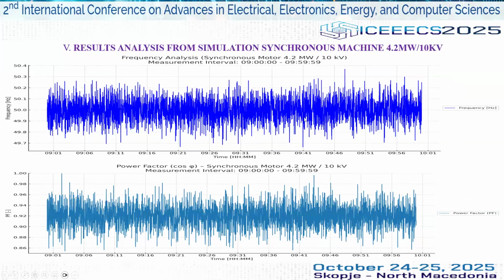The next picture illustrates the frequency analysis. The value remains very close to the nominal level of 50 Hz. The last picture presents the power factor. The power factor value remains high for most of the interval, indicating an efficient and well-compensated operating regime. Slight variation at higher current reflects the influence of the reactive component and the dynamics of the industrial process. The trend line confirms the overall stability of the power factor with respect to current demand.